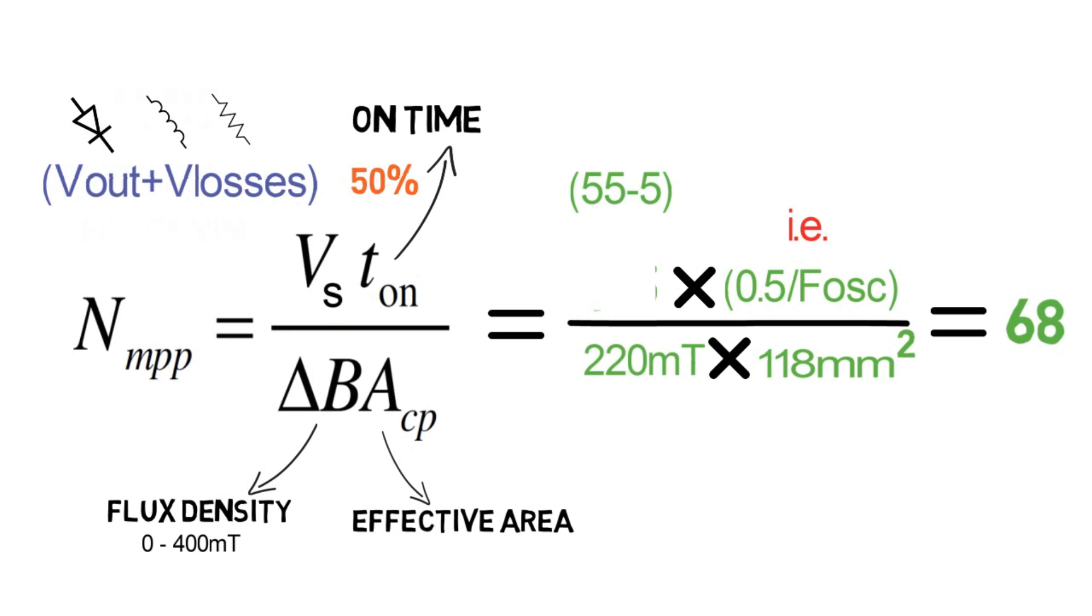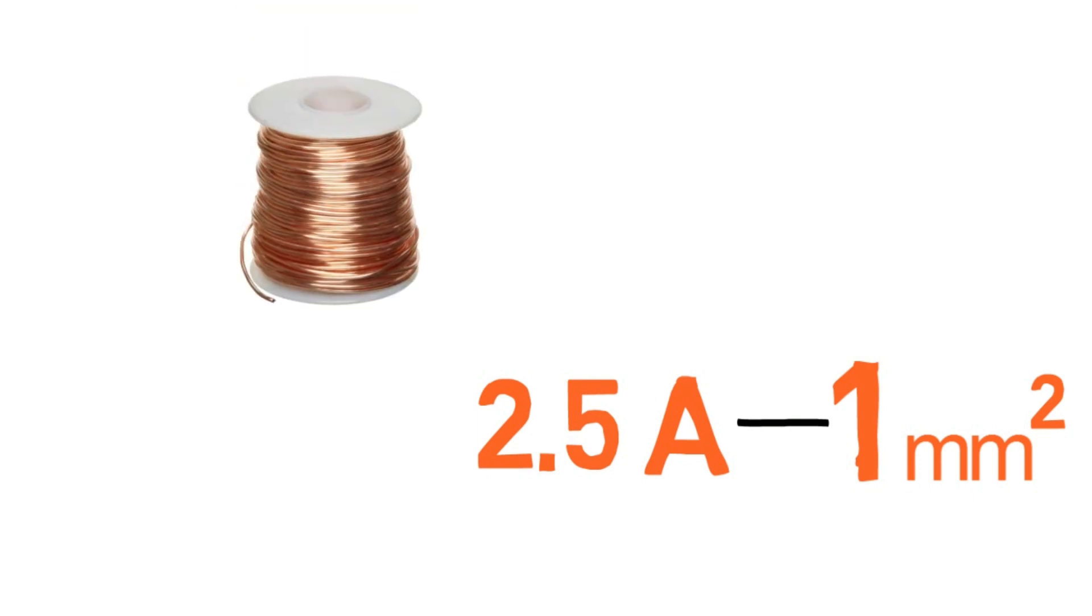Generally for 2.5 amps of current, 1 mm square cross-sectional area of the wire is sufficient. This is not the standard assumption, but if we increase this current value per mm square, then more heat will dissipate and heating losses will increase.